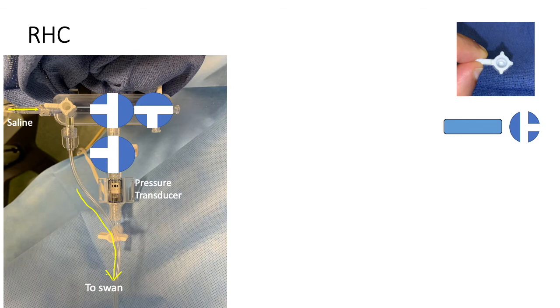Now if we were to change just one other thing, which is to move the valve adjacent to the saline port 90 degrees away from us, this would lead to alignment of the valves like this. And it would allow for the saline to come down. It could not get past the pressure transducer because it's a dead end. It would just lead to a bump in the recorded pressure.